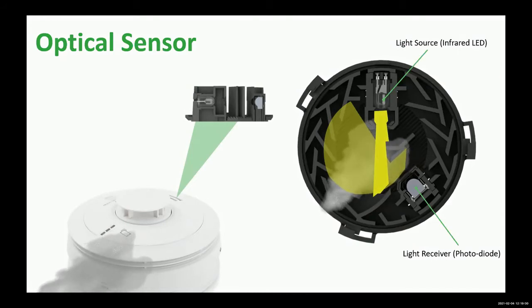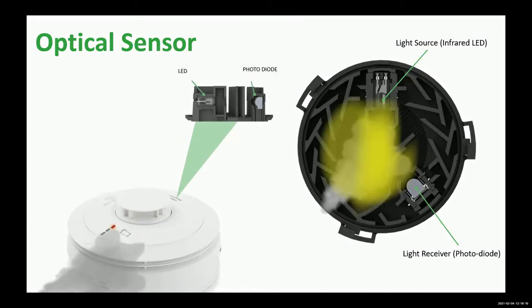And we're also looking at the light scattering principle. If you look there, there's no beam of light going into the light receiver. But once you get a high density of smoke, you get what they call the light scattering principle, and that scatters beams of light all over the chamber, and eventually you get a beam of light going into the receiver. That closes the circuit and sets the unit into alarm. Okay. That's the basic operation of the optical unit.